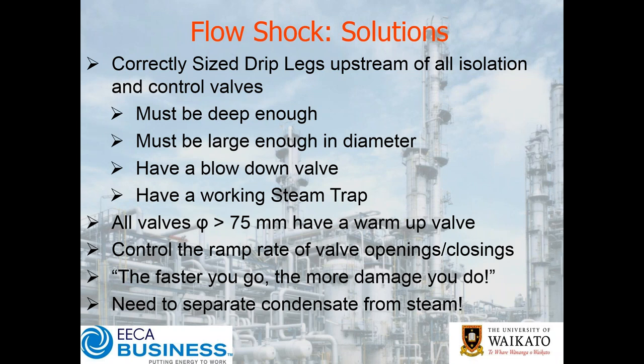What's our solution to eliminate flow shock water hammer? First, we need to correctly size our drip legs upstream of all isolation and control valves. There are really good tables available online through various suppliers that say, if you've got this size steam line, then you should have this size of drip leg — this diameter and this deep. The key thing is that drip leg needs to be deep enough and large enough in diameter so that the condensate doesn't get blown across it — it actually needs to catch the condensate.